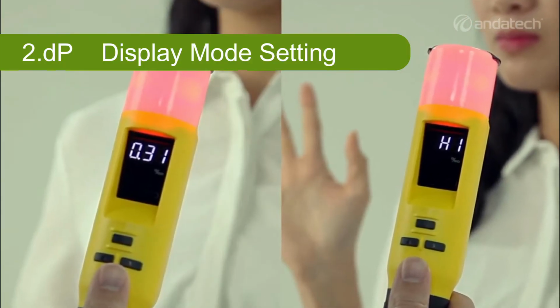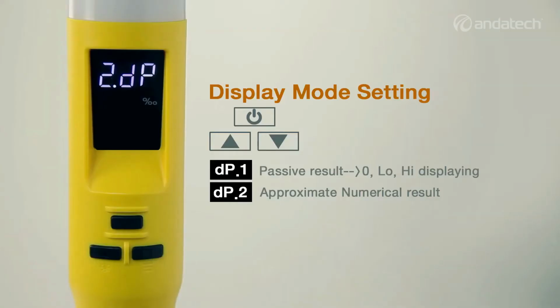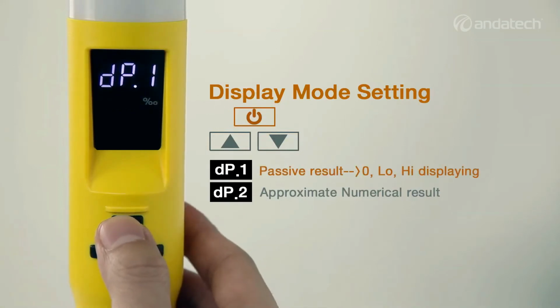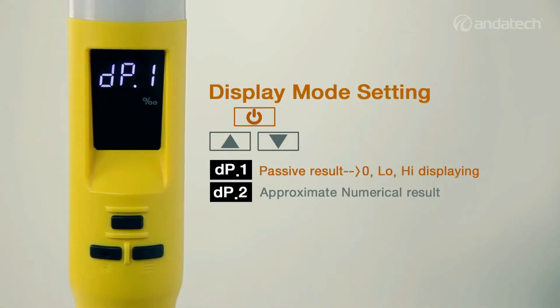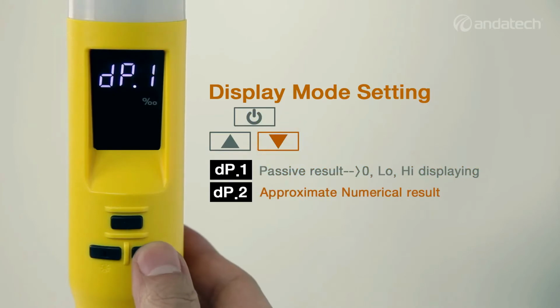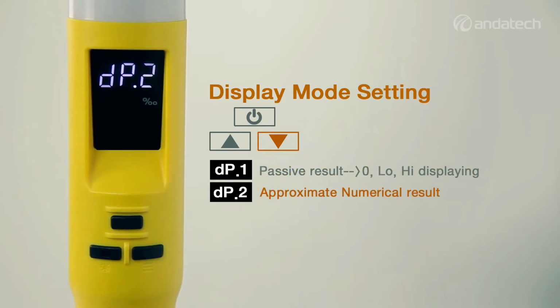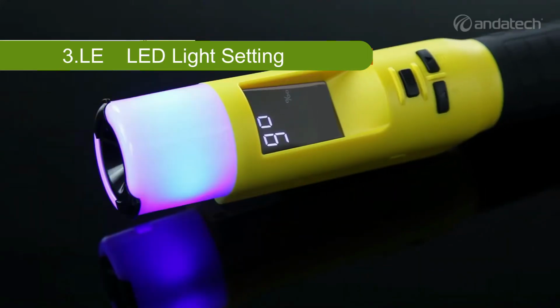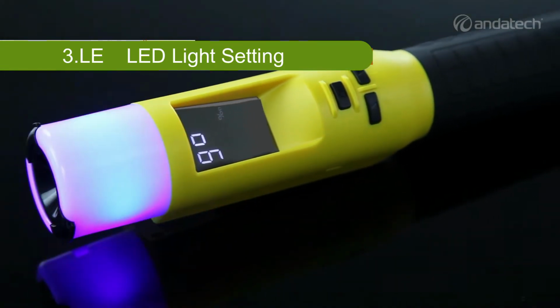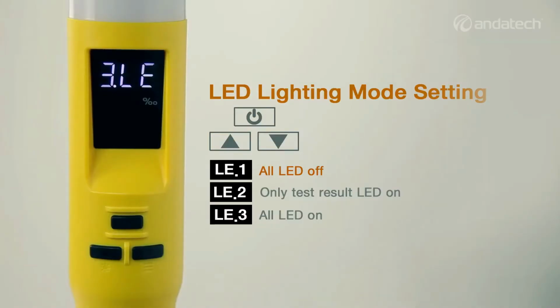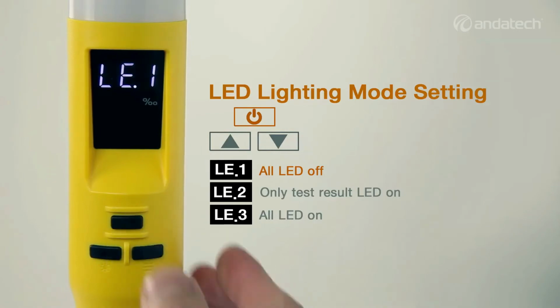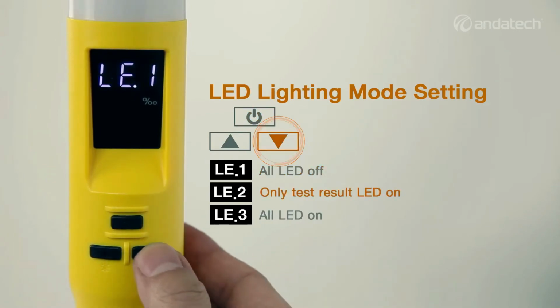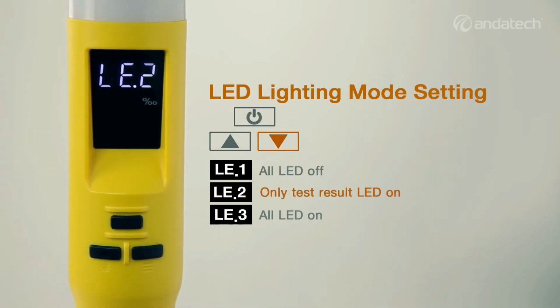2DP is the test result display mode, where DP1 indicates 3 levels, which are 0, low, and high, while DP2 indicates the approximate value in numbers. 3LE is the LED display mode. In LE1, all LED functions are turned off. LE2 shows only the test results. LE3 can be used in both standby and blow modes, and to display test results, while the light is always on.